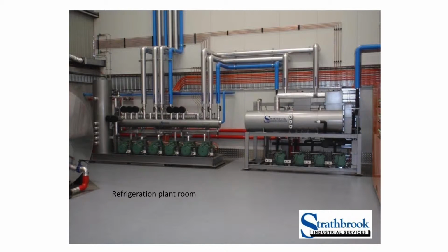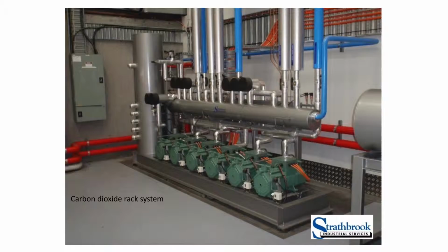So there's the CO2 system. That's running a 120 kilowatt freezer on the right-hand side with the low temp package. The 3 compressors on the right of the 6 compressor package are high stage for the freezer, and the other 3 compressors are doing 180 kilowatts of cool room and load out. So there's the transcritical system. You can see it's not that complicated. There aren't that many pipes. You can make this as complicated or as simple as you want.